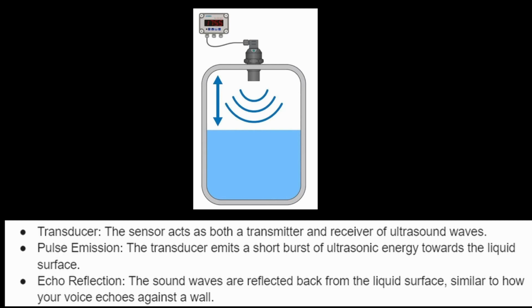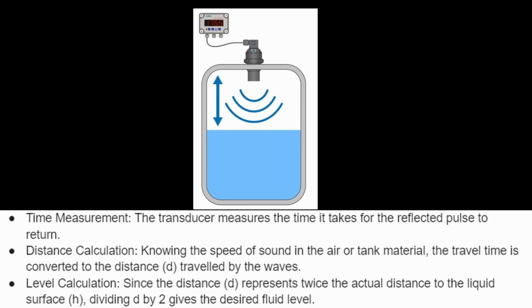Transducer. The sensor acts as both a transmitter and receiver of ultrasonic waves. Pulse emission. The transducer emits a short burst of ultrasonic energy towards the liquid surface. Echo reflection. The sound waves are reflected back from the liquid surface, similar to how your voice echoes against a wall. Time measurement. The transducer measures the time it takes for the reflected pulse to return. Distance calculation. Knowing the speed of sound in the air or tank material, the travel time is converted to the distance d traveled by the waves.